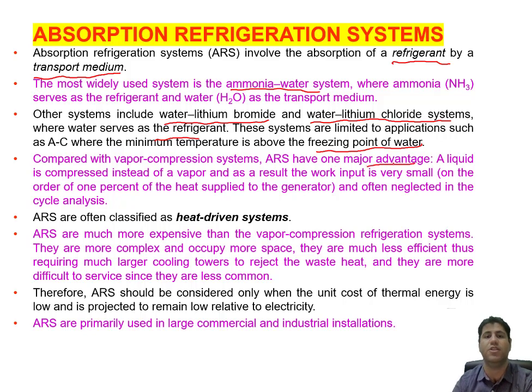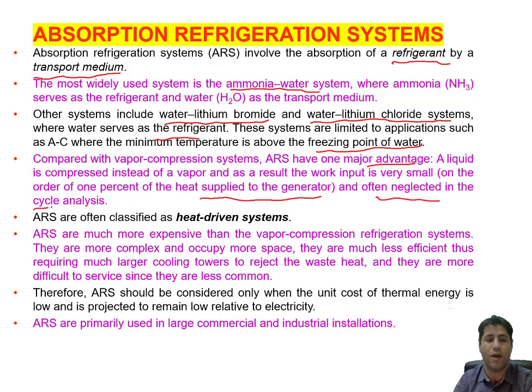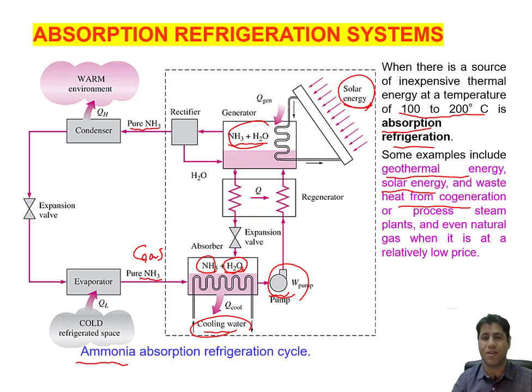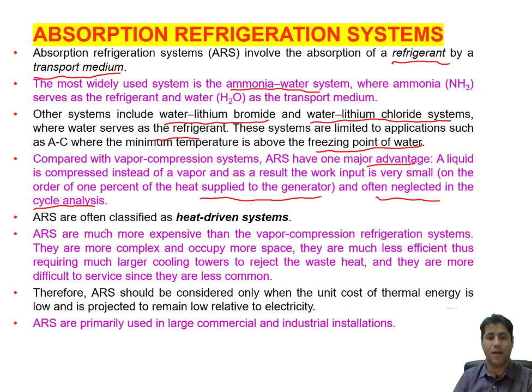Compared with vapor compression refrigeration systems, ARS have one major advantage: a liquid is compressed instead of a vapor. As a result, the work input is very small — on the order of one percent of the heat supplied to the generator. We usually neglect the pump work, and the only requirement for this cycle is the energy source, such as solar energy. ARS are classified as heat-driven systems.